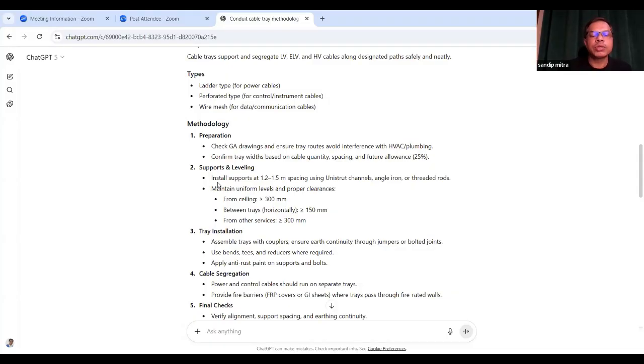Supports and leveling: install supports at 1.2 to 1.5 meter spacing using channels, angles, threaded rods, etc. Maintain uniform levels, and these are the clearances required: from ceiling, greater than or equal to 300 mm; between trays, greater than or equal to 150 mm.